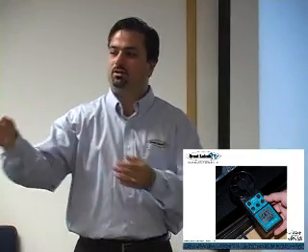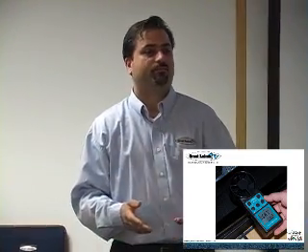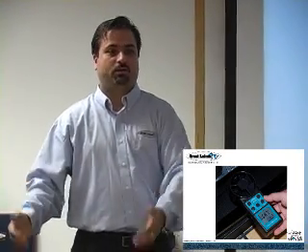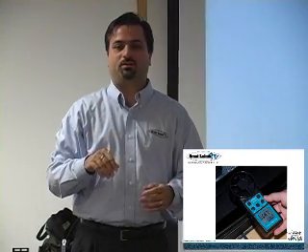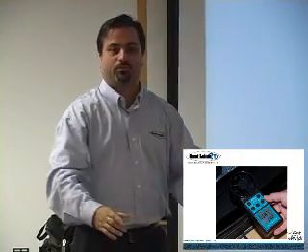Now that would be like going with a cold aisle perf tile. Instead of trying to get the perf tile air in the cold aisle through that mesh front door, we're now bringing it right to the front of that equipment. But all this equipment is designed to draw air through the machine, so some can draw more.